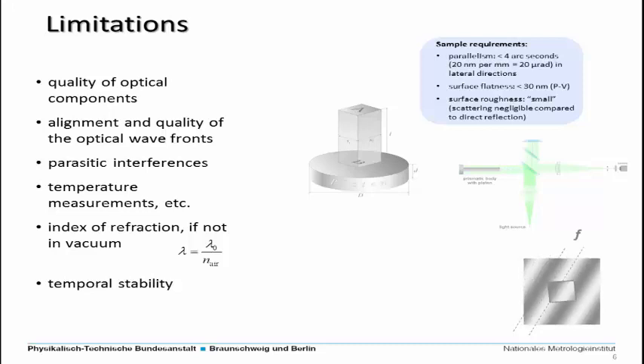For instance, the temperature measurement is very important. You may imagine that each temperature change directly has an influence on the length which we are measuring. That means we have to measure the temperature very precisely, depending on what uncertainty we are aiming at for the length measurement. Similarly, the index of refraction, if we are not working in vacuum, as Paul already said, is also a restriction for the uncertainty of the measurement, and the accuracy is reduced if you cannot determine the refractive index of air very precisely. Then we also have the temporal stability, which is also linked to temperature measurements. For example, if you are performing measurements over a longer time and you cannot make sure that the temperature is stable enough, then all this enters the result of the measurement.